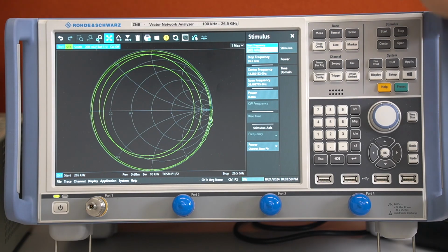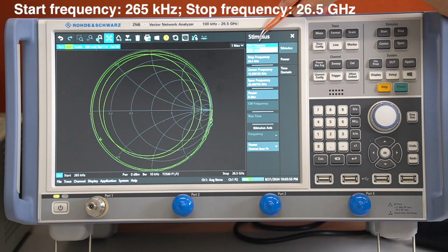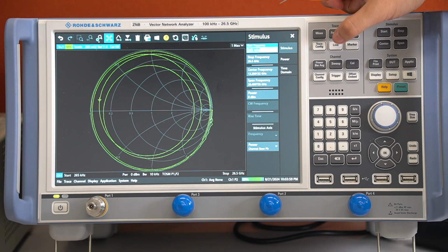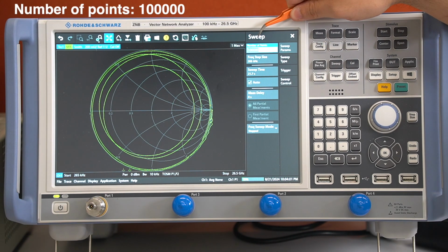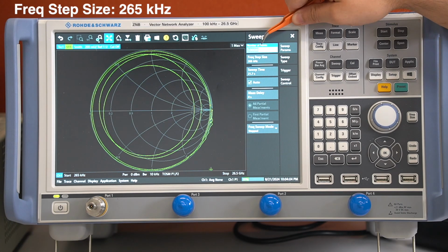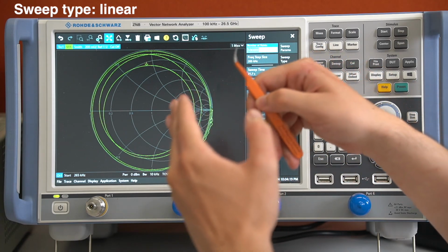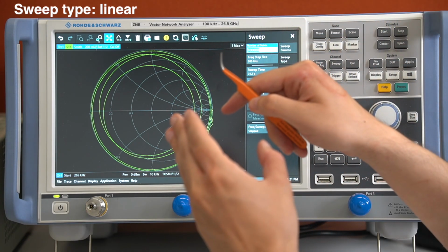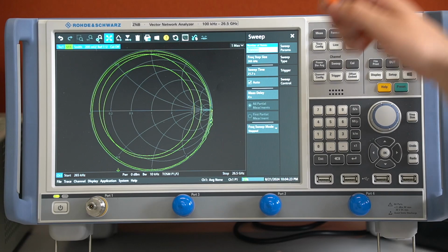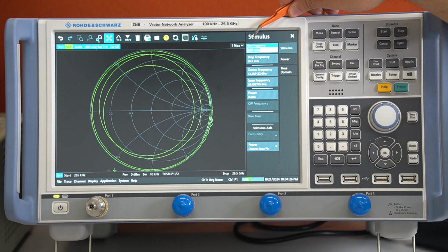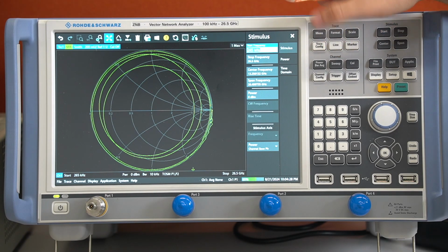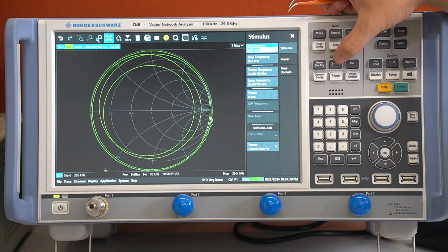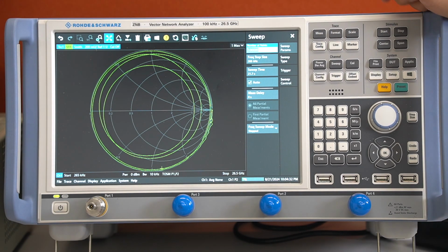Okay, I'm trying to get the full range of our VNA. So I'm starting at 265 kHz and stopping at 26.5 GHz. I've changed the number of measurement points to 100,000 with a step size of 265 kHz, resulting in a linear sweep with equal distance between each measurement point. So we are starting at 265 kHz and after each 265 kHz with the next measurement point.